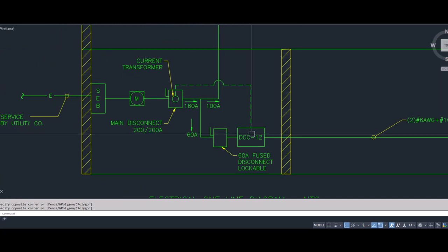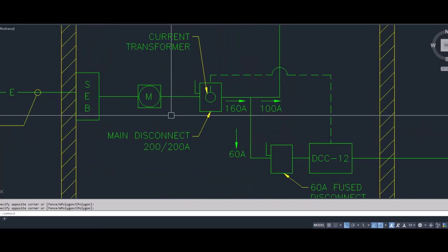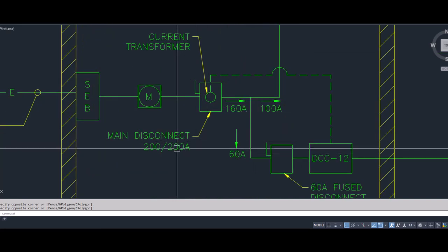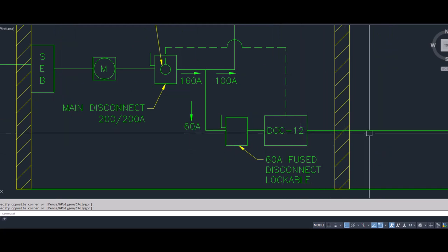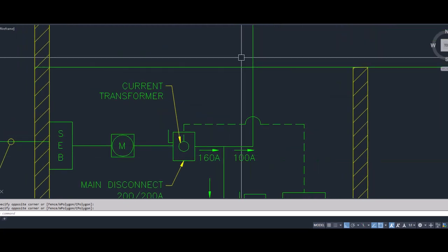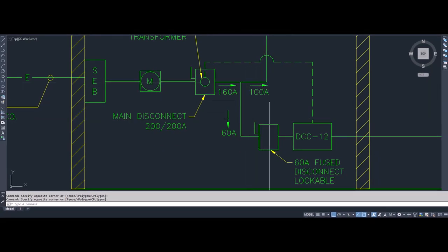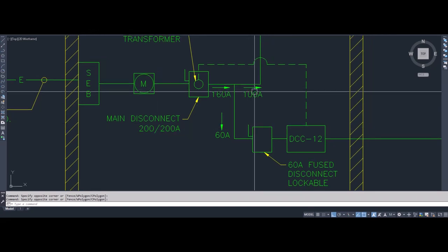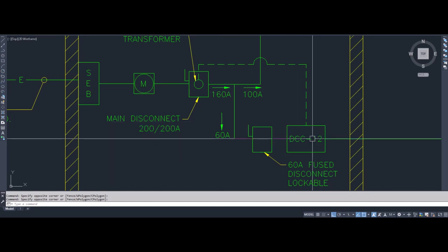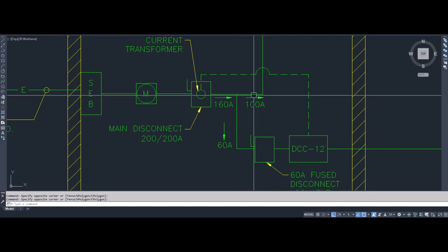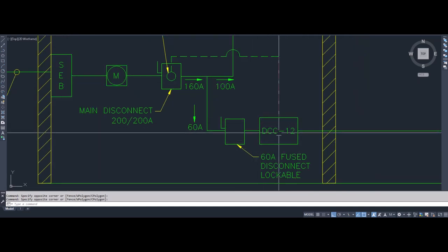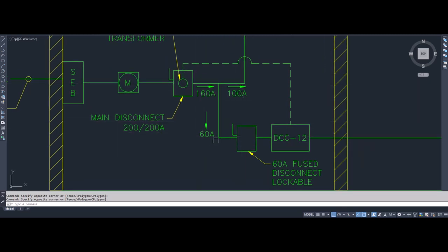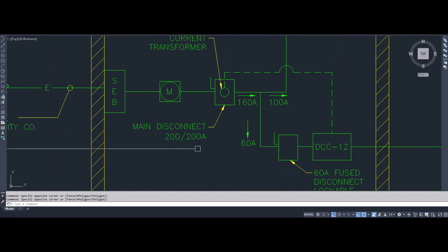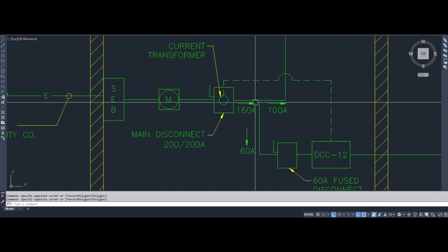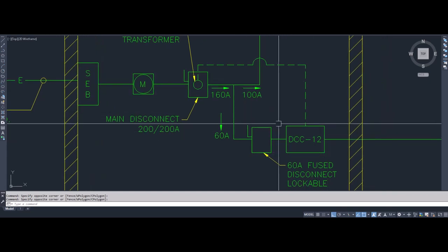So in this example, we have a DCC-12, so at 80% of the main disconnect, that's going to be at 160 amps, it's going to disconnect the power to the EV charger, sending all the power to your main panel. And let's say under normal usage, you have 100 amps. That means that under normal usage plus the 60, it will basically trip this DCC-12. But if your normal usage is at 100, you may not even need a system to disconnect the EV charger because your total is 160 amps, which is still less than your main disconnect, and it won't even trip your main disconnect during normal operation. So in those cases, you don't even need this type of system.